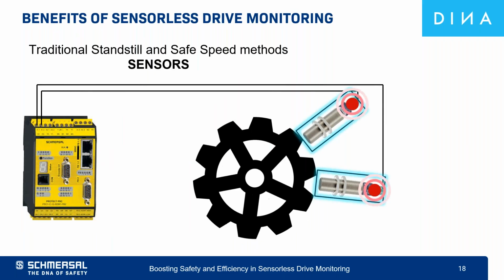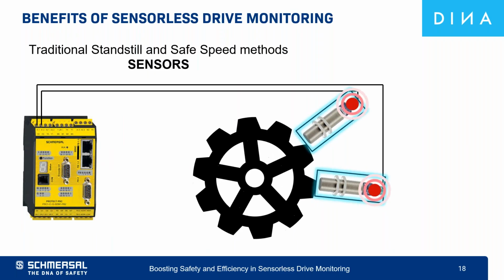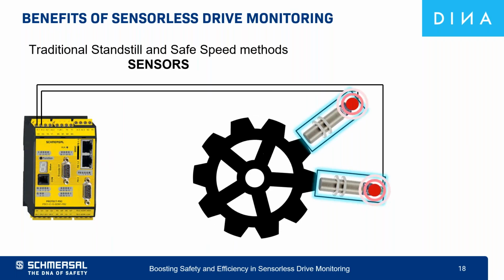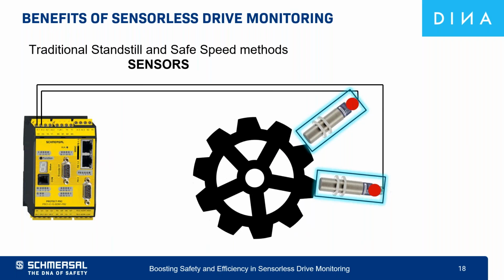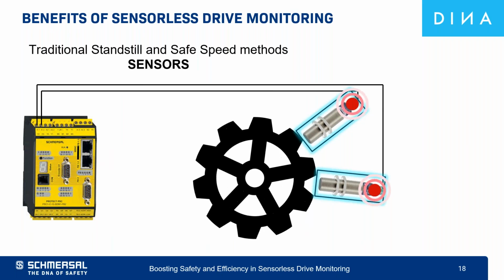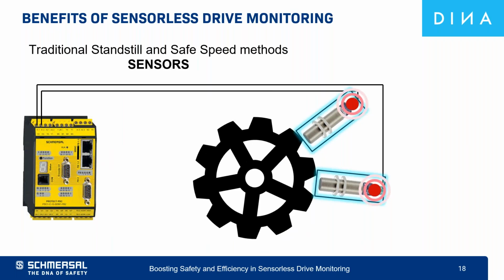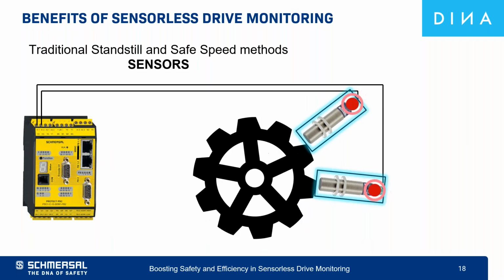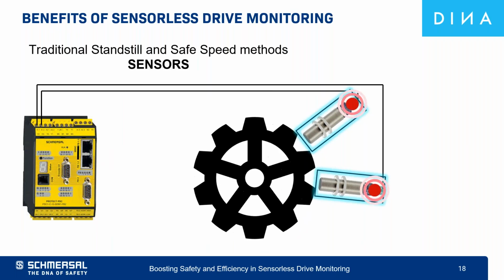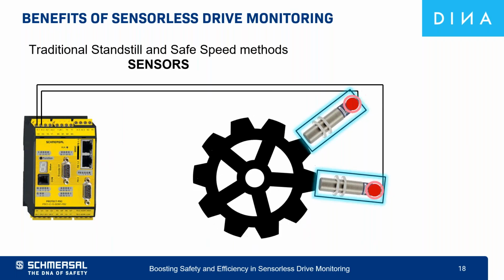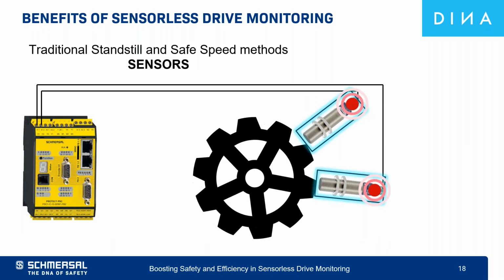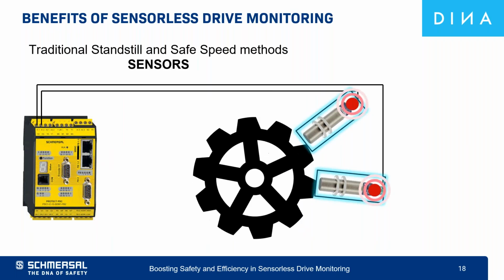The other variation of monitoring motion is to use two proximity switches to monitor a gear or a cog related to the hazardous motion. Proximity switches are not only not safe, but they're also devices which can be easily broken in the field by somebody simply working close by, or by environmental conditions or cleaning. Many times proxy switches are replaced in these systems with alternative proxies as well, which are not like-for-like, and that can give faults causing downtime.